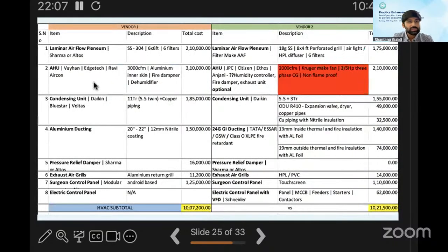So again, using this BOM, we'll see what the HVAC is comprised of. The first thing is the plenum, which is of various sizes. As mentioned, it can be 6 by 6 or 8 by 4, whatever you can plan. Then the air handling unit, which has a CFM value, which again I'll be talking about. It has a condensing unit, which, as you see here, is mentioned as 5.5 twin or 5.5 plus 3 ton. So there are basically 2 condensing units, so that if one fails, the other keeps on functioning and you don't have to stop the OT. And also in India, in some places, about 8 ton is actually required to keep the temperature in the required standard.